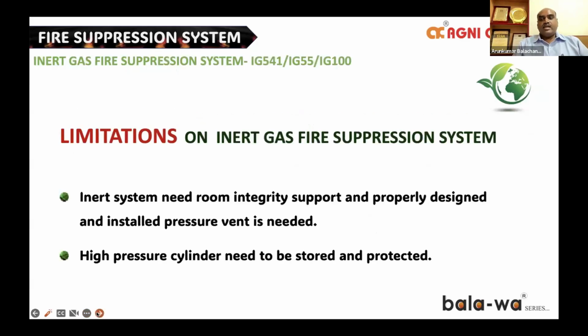When it comes to inert gas suppression systems, one of the important limitations is that it requires high room integrity, and a properly designed and installed pressure vent is required. Without room integrity, an inert system is not advisable because it will bring down the entire false floor or false ceiling. And these being 200 or 300 bar systems, they are stored in high pressure cylinders, and they need to be stored, handled, and protected properly.